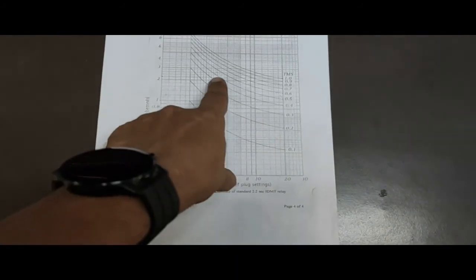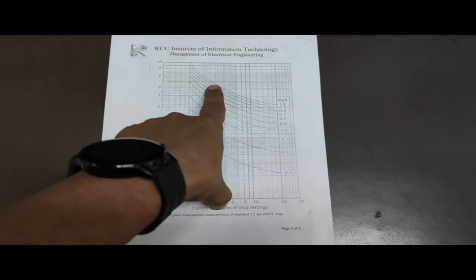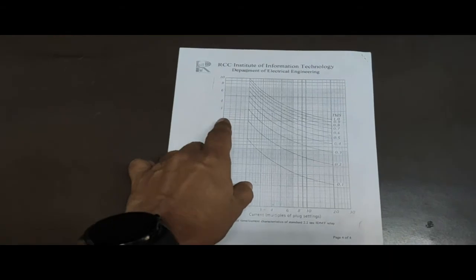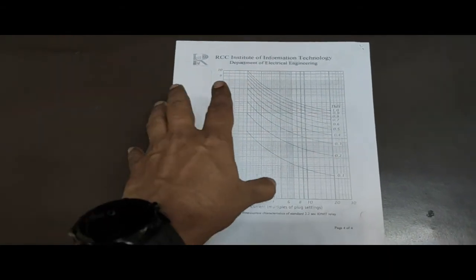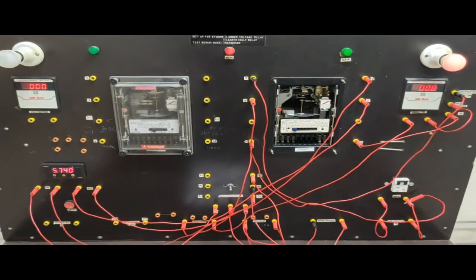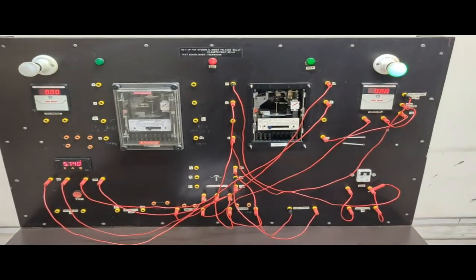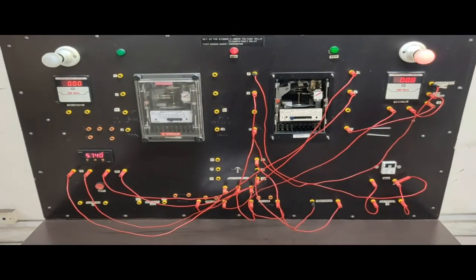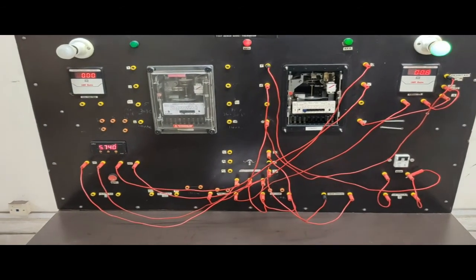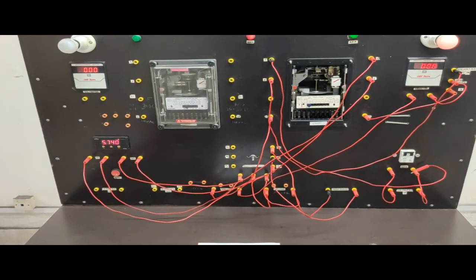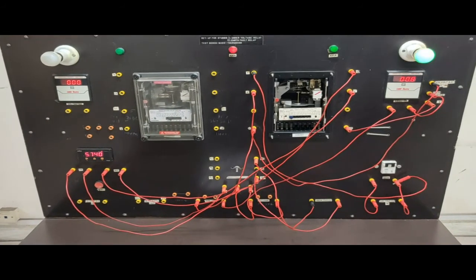So that means find the intersection of this line and the first curve, and from this characteristics curve or IDMT curve you need to find the theoretical time required to operate the relay, and from this timer you can get the actual relay operating time. So in this way you need to take at least 5 readings to make a characteristics curve or IDMT characteristics, and this is the operation of the earth fault relay.